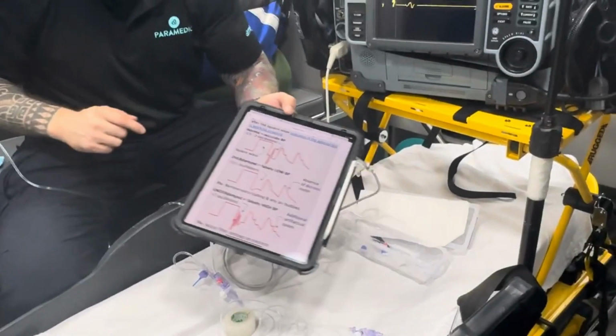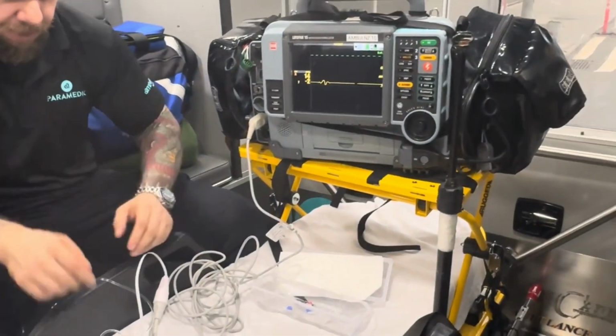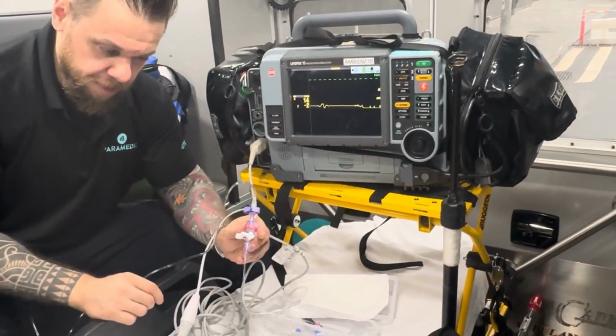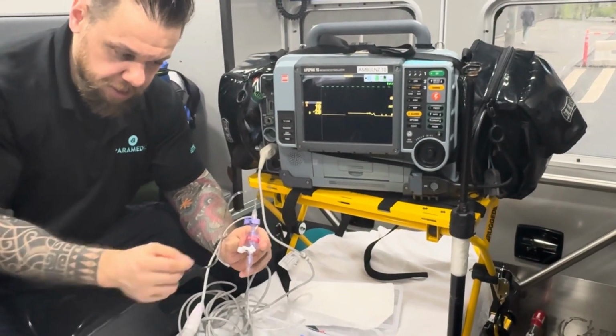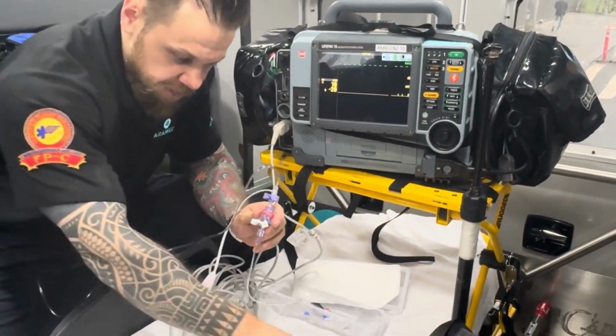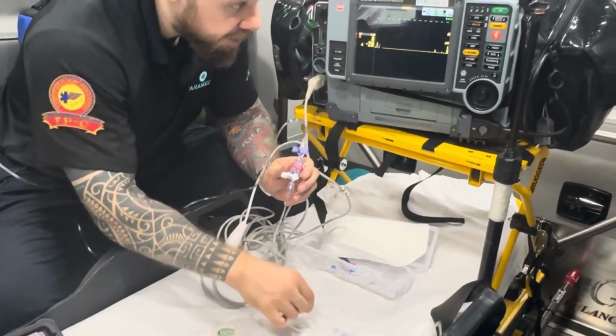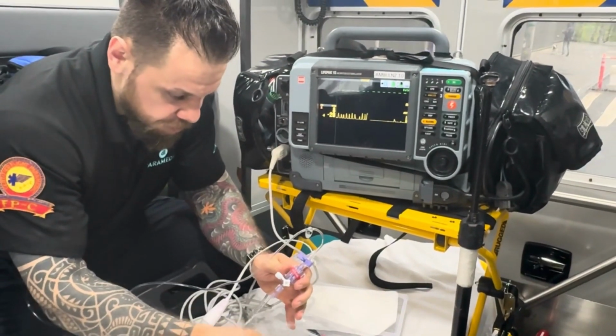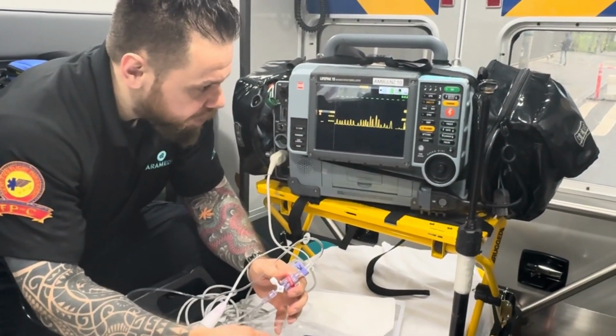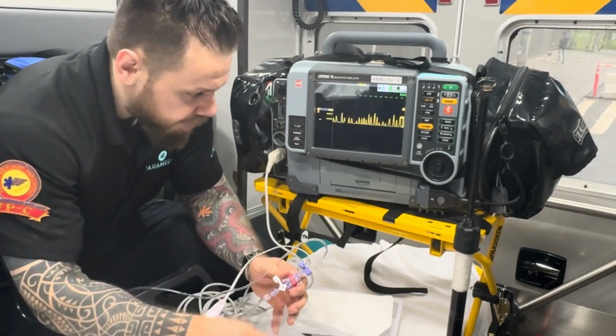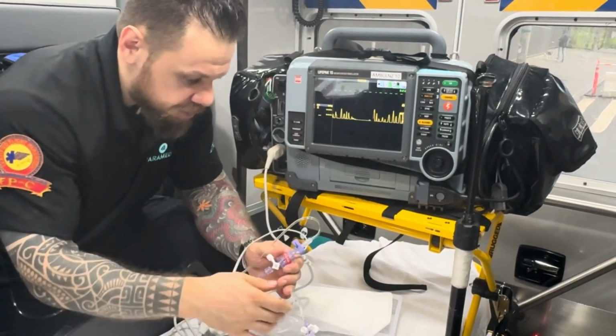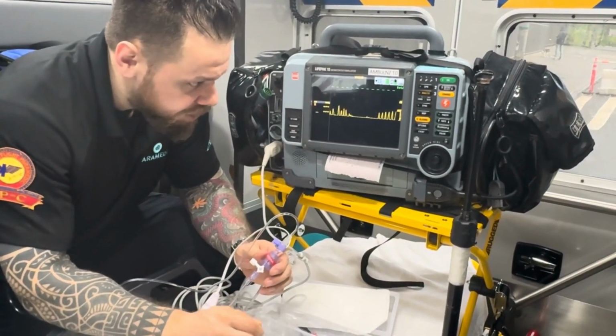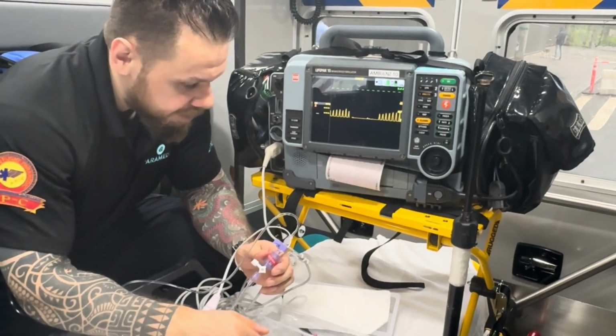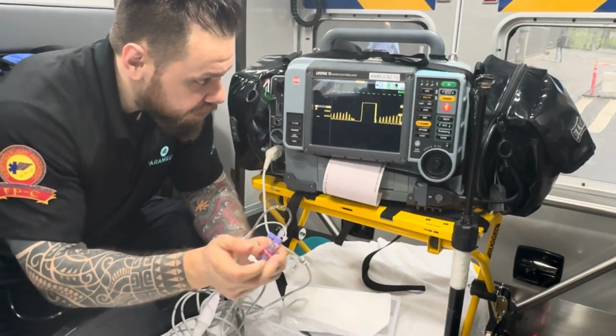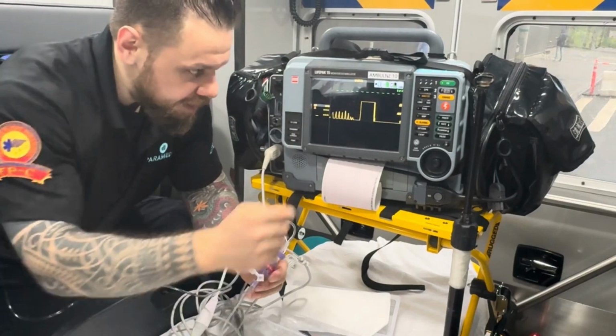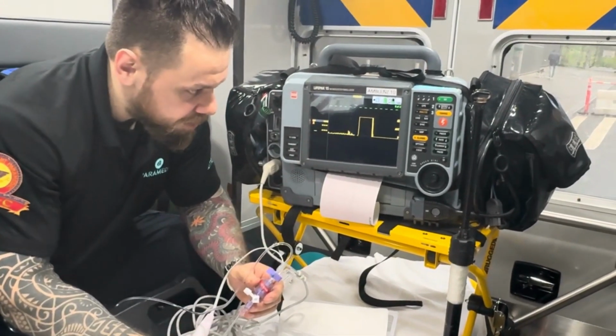So let me come back to the monitor. To perform a fast square flush test, I'm going to pull on this pigtail real quickly. So pretend I'm going to hit this, and the blood pressure is going. Let's say the patient has a BP of 90/60. What I usually do is click print, so the EKG is coming out. And then I perform a fast flush test. You see the square waveform, and then I quickly look at what happens with my oscillation.